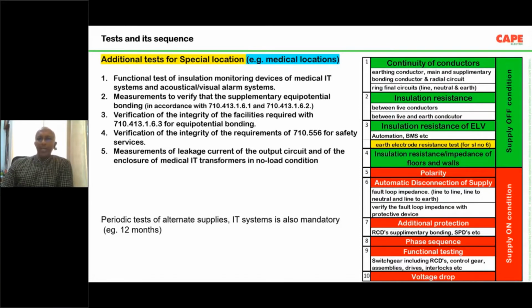So basically, there is a standard which talks about how to design, erect and test an installation, and I started from the last one, how to test a building, and the first test is called continuity of conductors. What do we mean by continuity of conductors? Continuity means you have a copper wire in your building, maybe a 2.5 square mm wire. It starts from the MCB distribution board, goes to a switch socket, then finally goes to some apparatus, maybe a fan or an air conditioner or whatever.